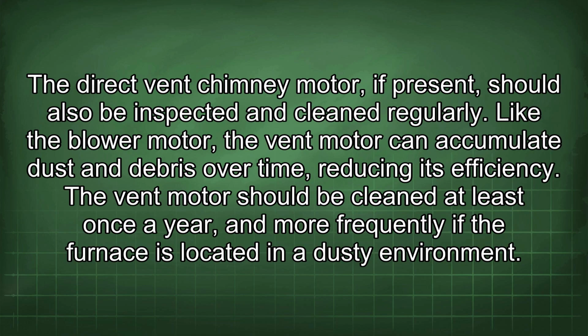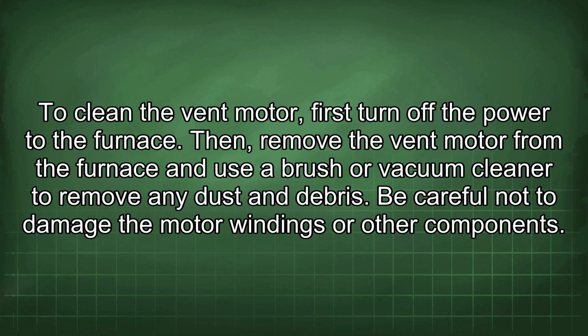The direct vent chimney motor, if present, should also be inspected and cleaned regularly. Like the blower motor, the vent motor can accumulate dust and debris over time, reducing its efficiency. The vent motor should be cleaned at least once a year, and more frequently if the furnace is located in a dusty environment. To clean the vent motor, first turn off the power to the furnace. Then, remove the vent motor from the furnace and use a brush or vacuum cleaner to remove any dust and debris. Be careful not to damage the motor windings or other components.